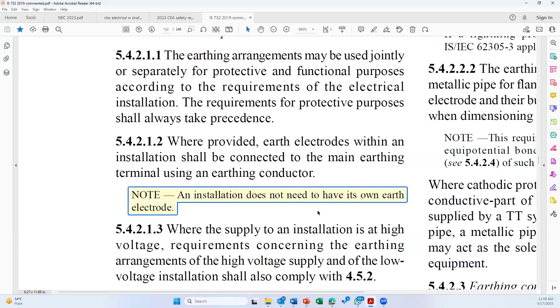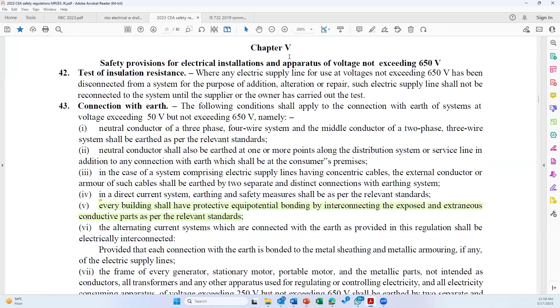That means you have a large industry, you have a transformer outside the building, that is a different thing, but inside the building you are using voltages less than 1000 volt AC, and maybe you have a rooftop solar PV which is maybe 800 volt DC. So in such cases, "an installation does not need to have its own earth electrode" is the correct information. If we go to the CEA regulation, Regulation 43 also talks about this particular subject. And for your information, in Regulation 43, a lot of changes happened in the 2023 regulation.